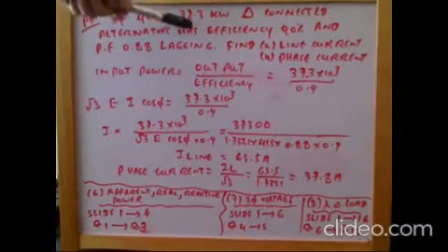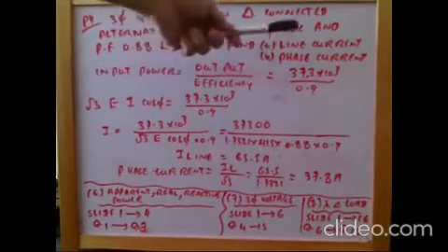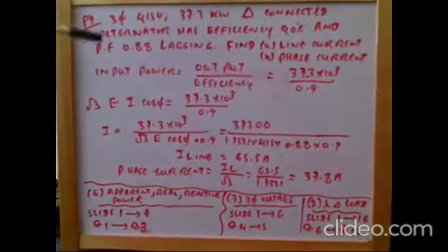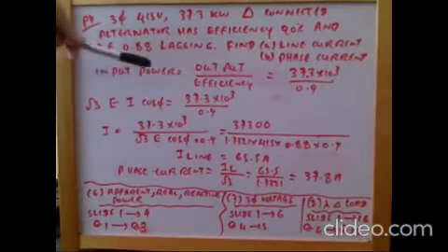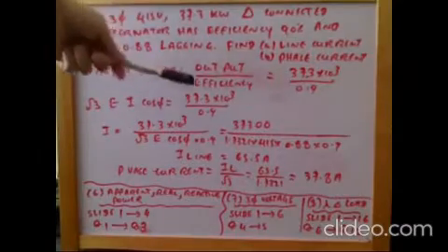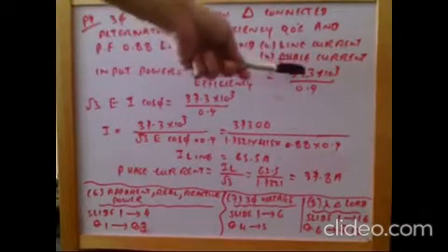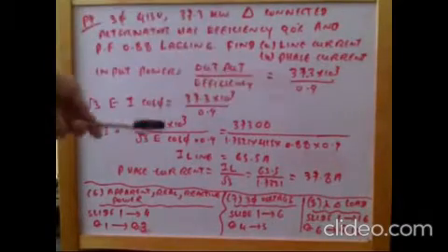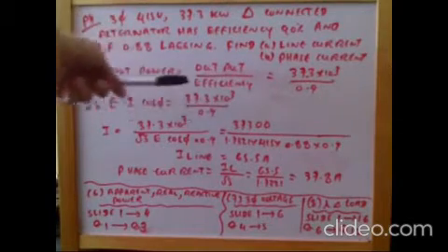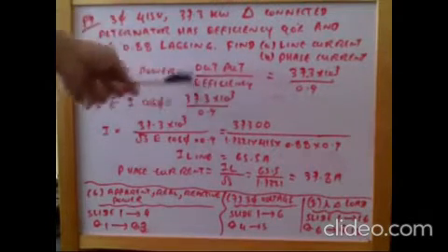This problem involves a three-phase system: 415 V, 37.3 kW, delta-connected, with 90% efficiency. We need to find the line current and phase current. First, we calculate the input power. The output power is 37.3 kW, and input power equals output divided by efficiency: 37.3 kW divided by 0.9.